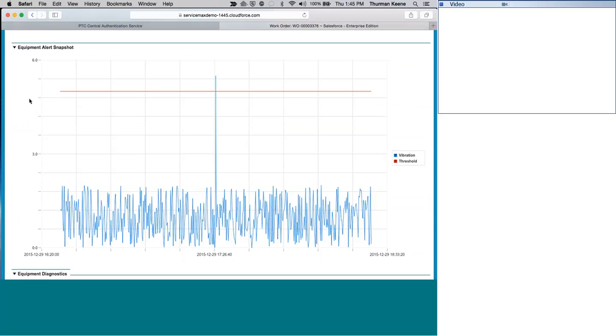Because we're monitoring different types of sensors on this piece of equipment, we set up a threshold within ThingWorx on our machine data. We're monitoring vibration, and we want to set up thresholds that say if these are exceeded, action needs to happen, and you can define what that action is. In this example, we've taken a snapshot automatically and said this work order was created because the vibration on this MRI machine exceeded its acceptable tolerance.